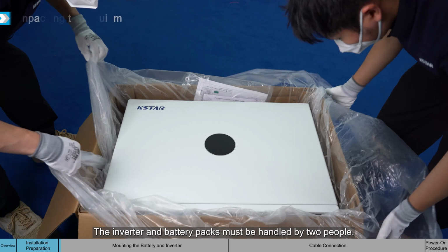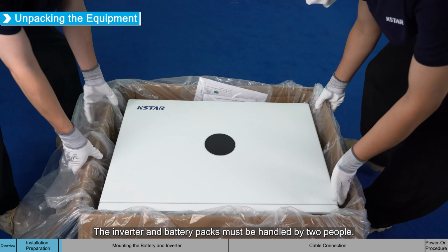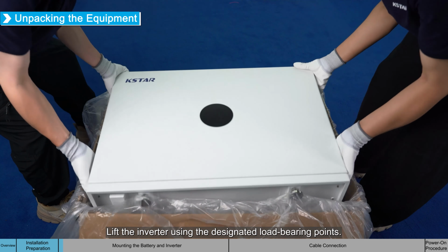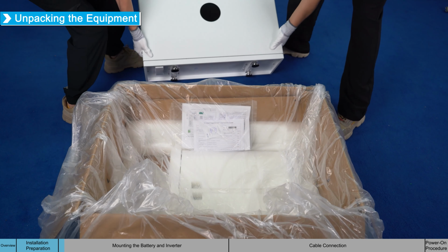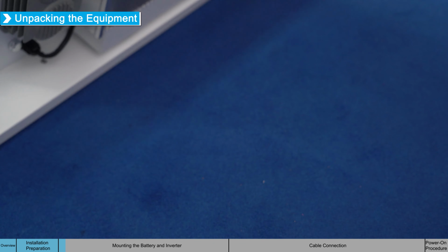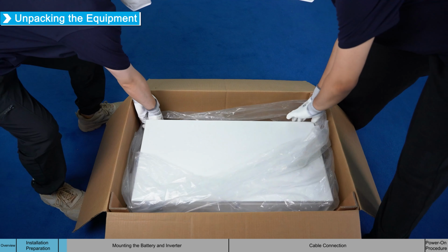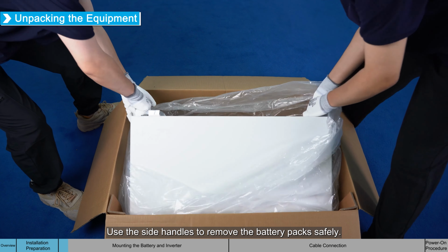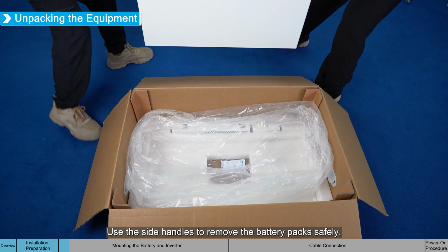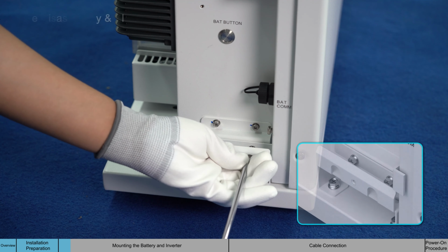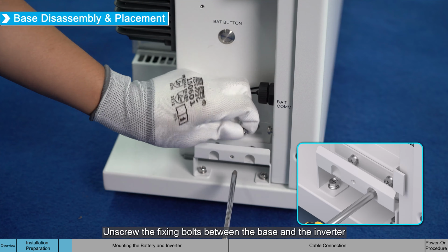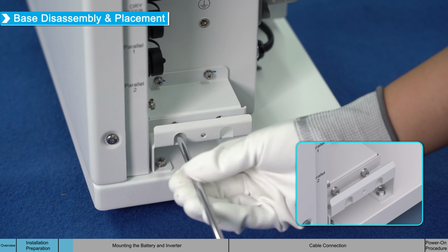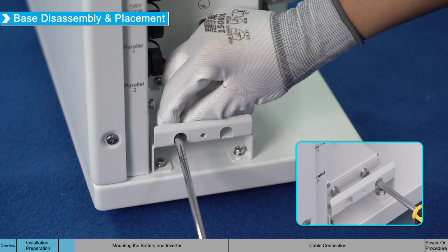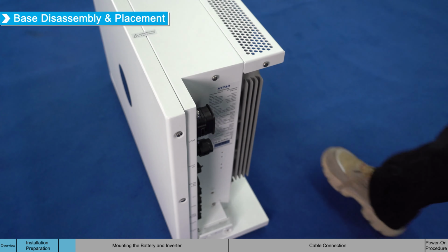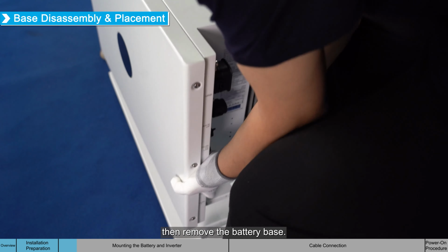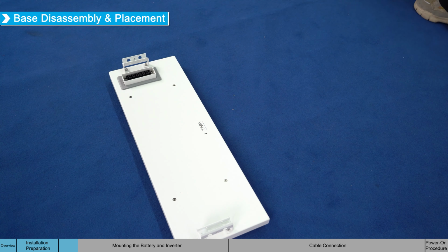The inverter and battery packs must be handled by 2 people. Lift the inverter using the designated load-bearing points. Use the side handles to remove the battery packs safely. Unscrew the fixing bolts between the base and the inverter. Then remove the battery base.